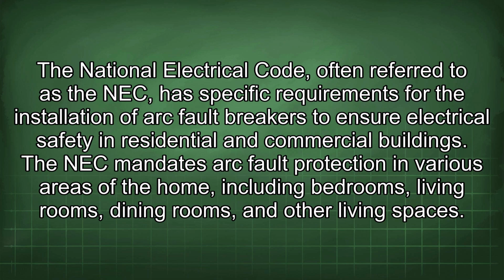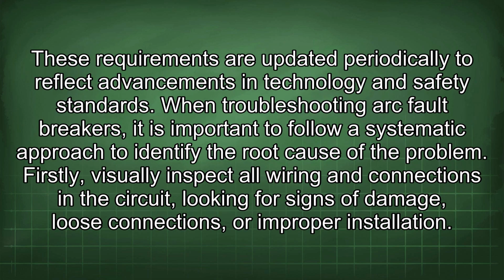The NEC mandates arc fault protection in various areas of the home, including bedrooms, living rooms, dining rooms, and other living spaces. These requirements are updated periodically to reflect advancements in technology and safety standards. When troubleshooting arc fault breakers, it is important to follow a systematic approach to identify the root cause of the problem.